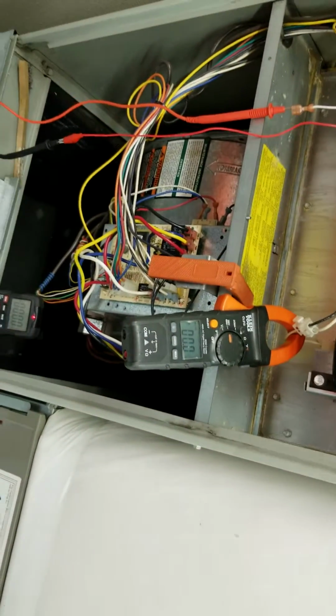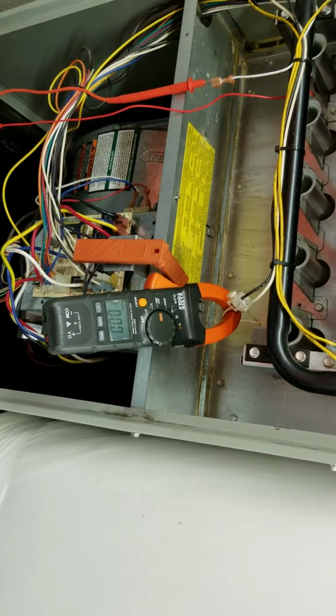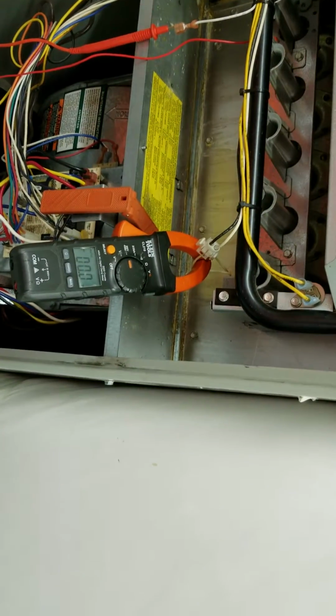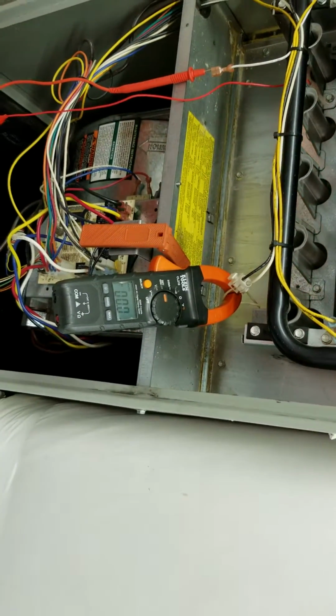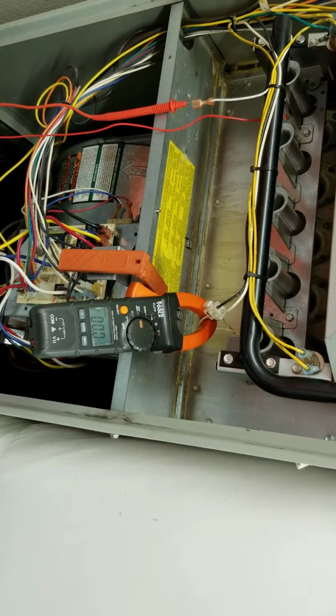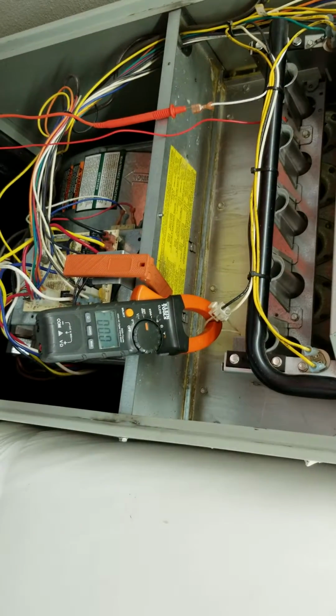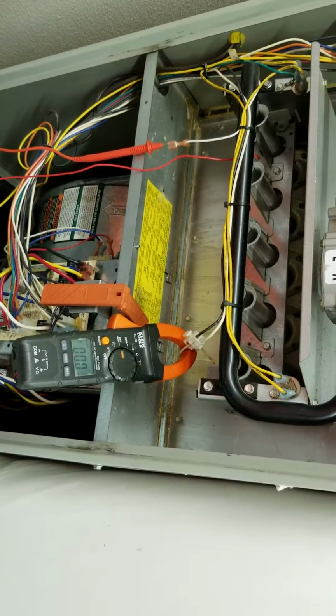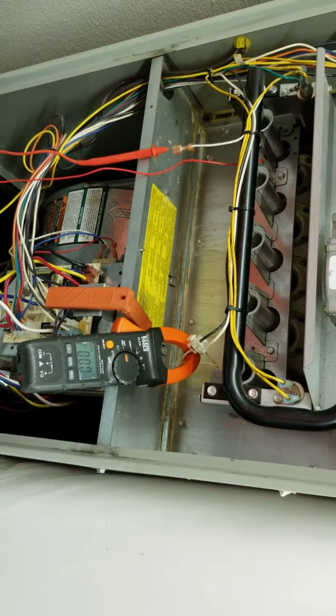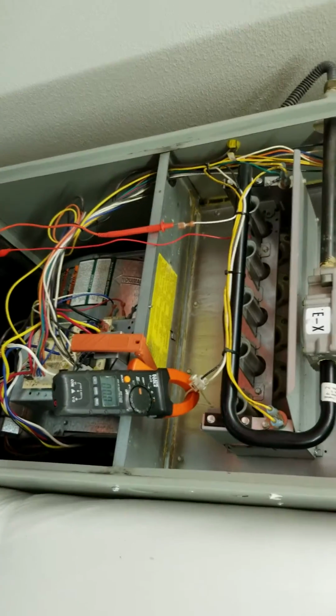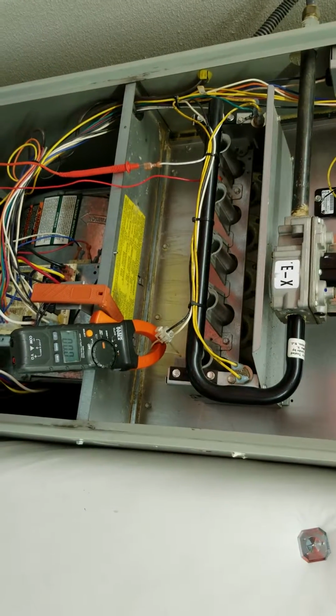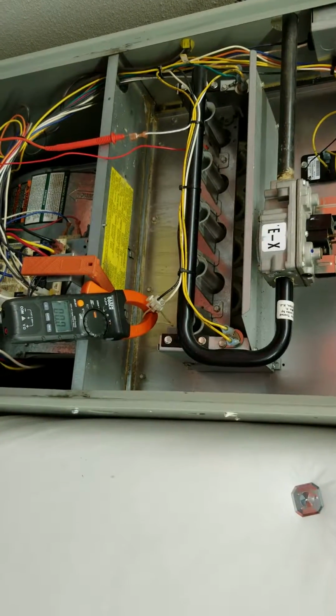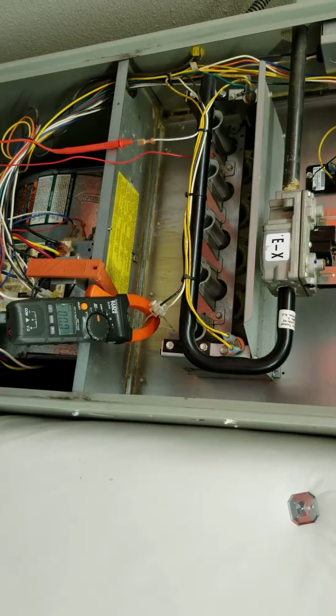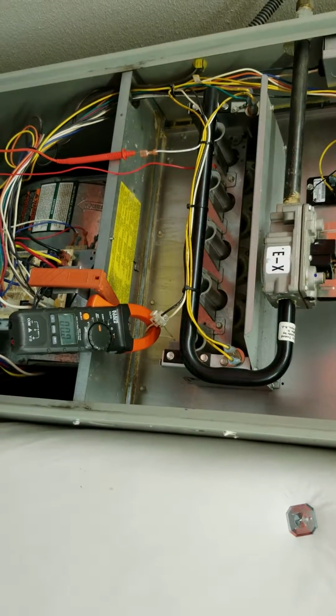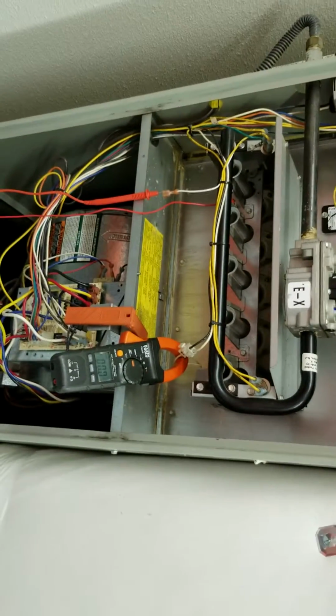Okay, now this furnace has a device on it in the control board that when the power has been off, when you energize the furnace controls, when there's an actual call for heat still on the thermostat, it runs for approximately 90 seconds to make sure that the heat exchanger does not get overheated and break it. So we're now waiting for that to cycle down and then restart. Hurry up and wait.